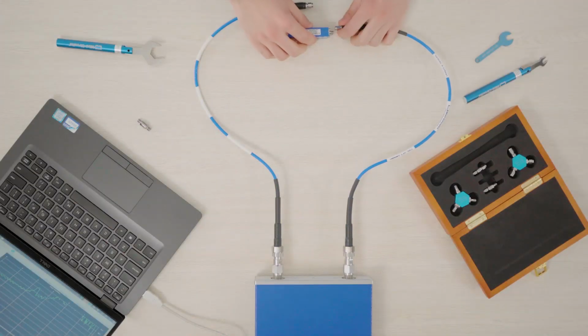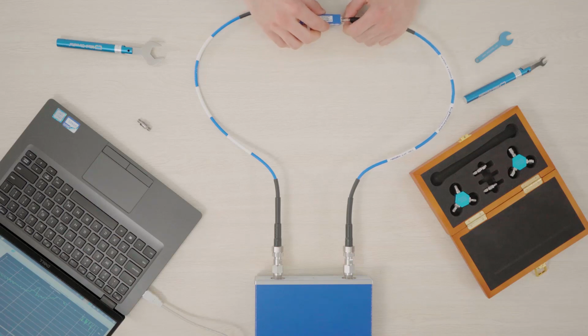At this point, we're ready for calibration. I'll be doing a full two-port calibration for the best possible accuracy. Check out our video on calibration to review the full calibration procedure. Once the calibration is complete, connect the DUT to the eVNA ports.